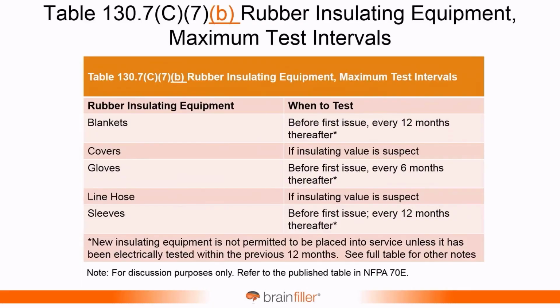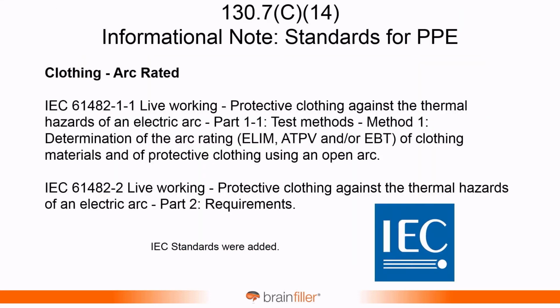And then the original table has just been given a B designation, 130.7C7B, so that is still there. This was another change. I actually got kind of involved in this one. For PPE testing and arc-rated PPE, historically, NFPA 70E has referenced ASTM standards. And the last cycle, all of those standards were moved to a table referenced by an informational note. They were basically taken out of the mandatory part of the text.